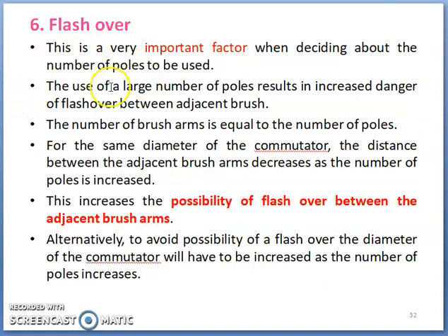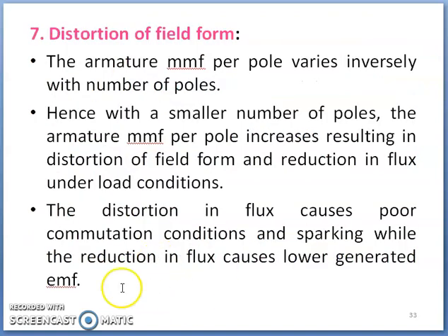Coming to flashover: this is a very important factor when deciding the number of poles. If a large number of poles are used, there is an increase in the danger of flashover between two adjacent brush arms. The number of brush arms equals the number of poles, and for the same diameter of commutator, the distance between adjacent brush arms decreases as the pole number increases. Hence, there is an increased possibility of flashover between adjacent brush arms, which can be avoided by increasing the diameter of the commutator. Coming to field form: armature MMF per pole varies inversely with number of poles, and hence distortion of flux will cause commutation problems.